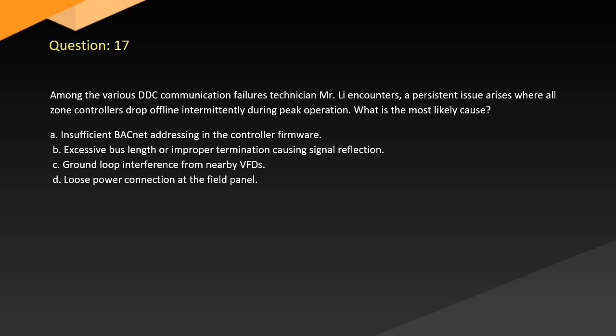Question 17. Among the various DDC communication failures technician Mr. Li encounters, a persistent issue arises where all zone controllers drop offline intermittently during peak operation. What is the most likely cause? A. Insufficient BACnet addressing in the controller firmware. B. Excessive bus length or improper termination causing signal reflection. C. Ground loop interference from nearby VFDs. D. Loose power connection at the field panel.